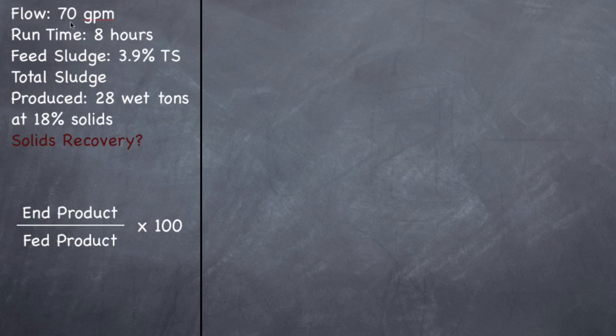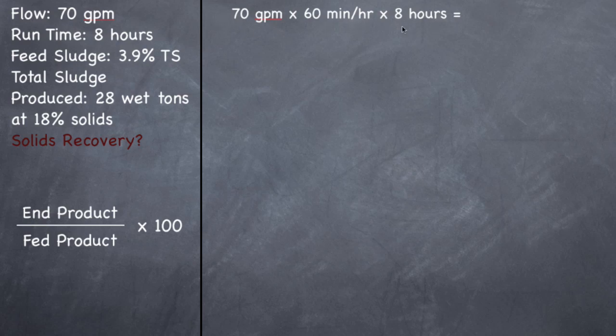Whenever you're doing pounds, you need MGD. This is gallons per minute, so 70 gallons per minute times 60 minutes in an hour gives you gallons per hour, and then it's run for 8 hours — that gives you the total gallons for that run time. So 70 times 60 times 8 gives you 33,600 gallons per day.